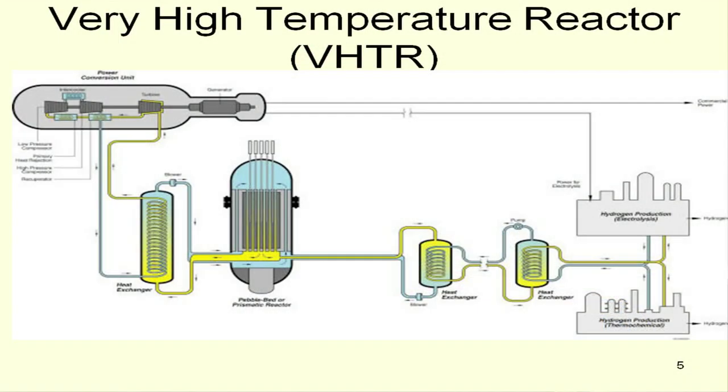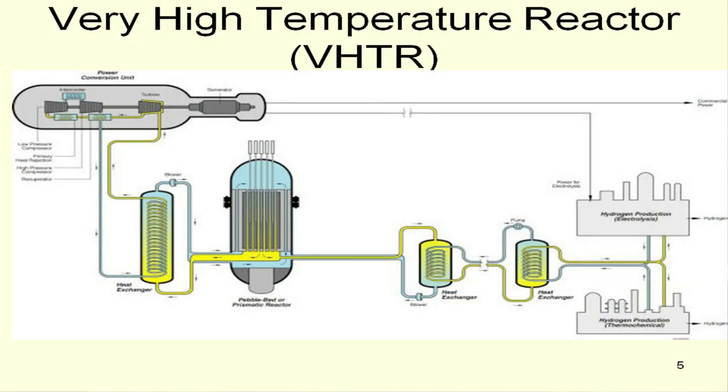Sort of a cartoon of it, and it's not unobvious. This one shows process heat application over here, where you go through a secondary heat exchanger. Actually, this has a primary loop and then secondary and a tertiary to isolate the radioactive stuff from whatever process you've got over here. And in this reactor, there are questions being asked. You know, what is the coupling between these folks over here, which aren't going to be licensed by the Nuclear Regulatory Commission, and over here? And if something happens here, can it mess up the reactor? And that hasn't been run to ground yet. It's still an issue under discussion.